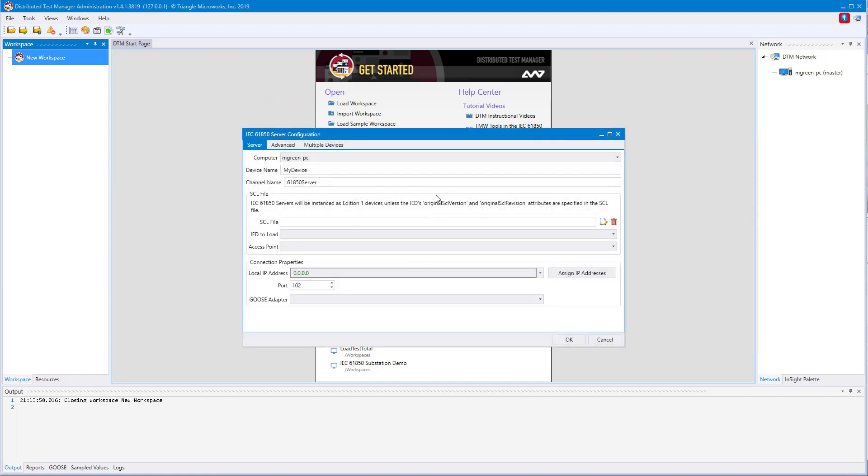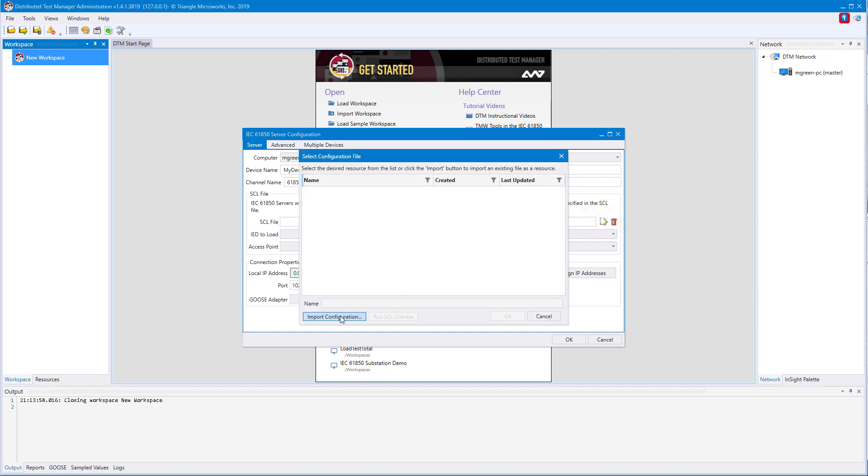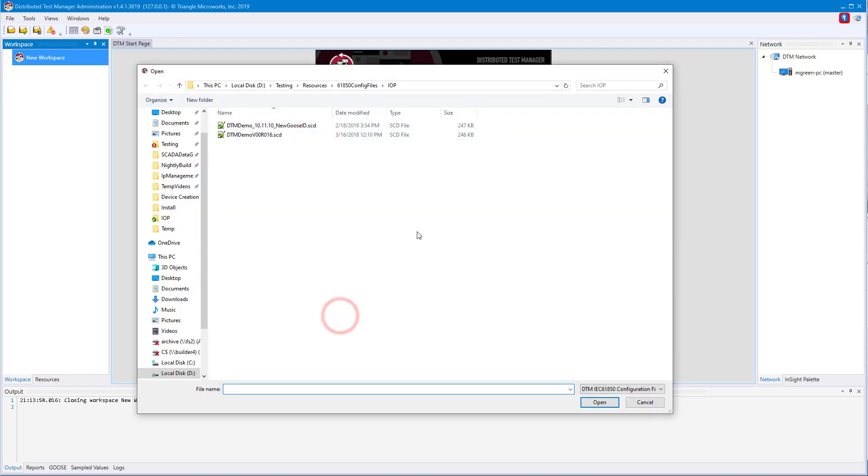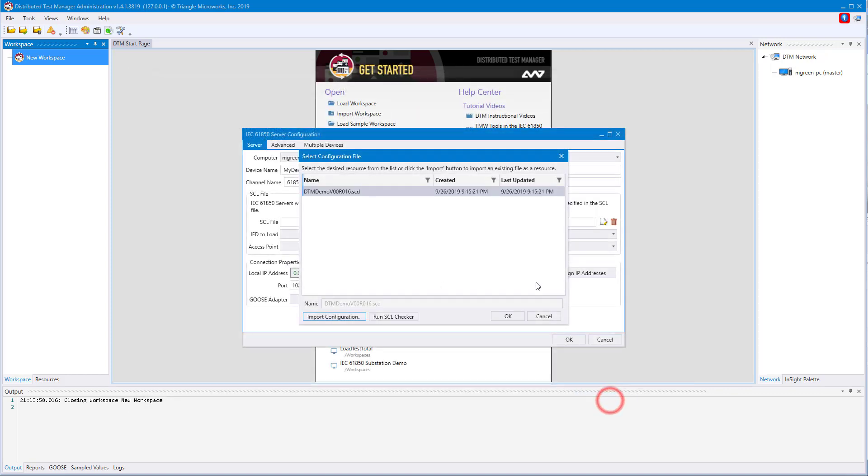IEC 61850 uses configuration files that we can import directly into DTM to simulate those devices. DTM supports many forms of these configuration files, including ICD, CID, SCD, and many more file types. You can do this by clicking the SCL file icon and clicking Import Configuration. From here, just navigate to your file, select it, and hit Open.